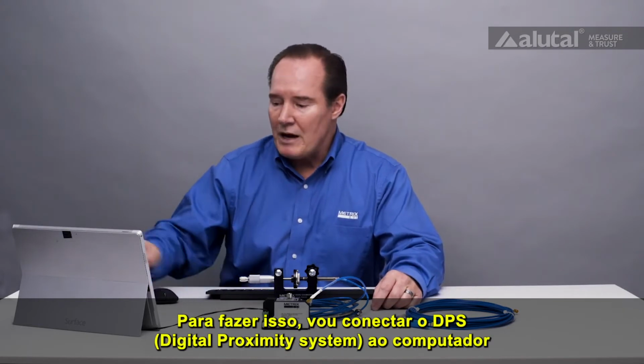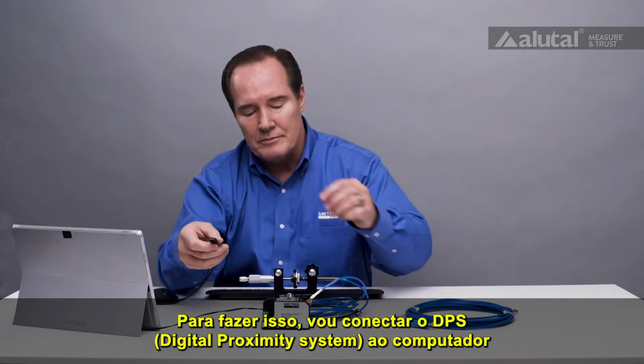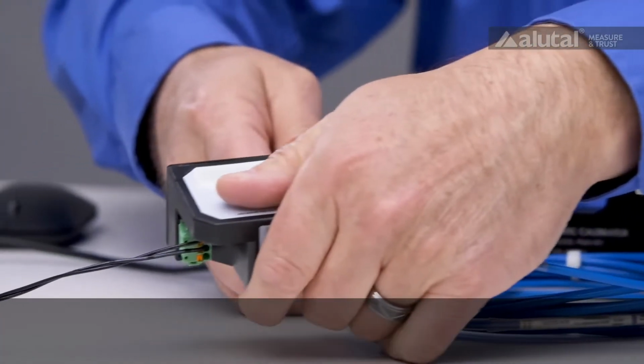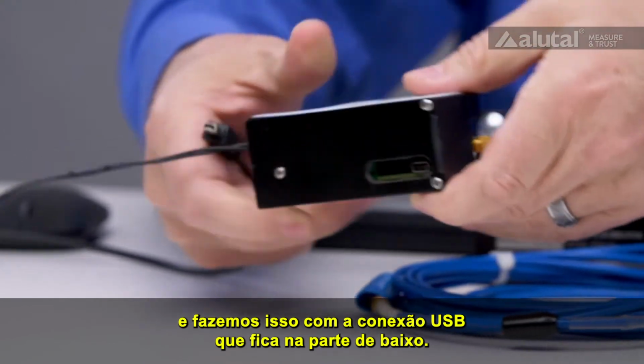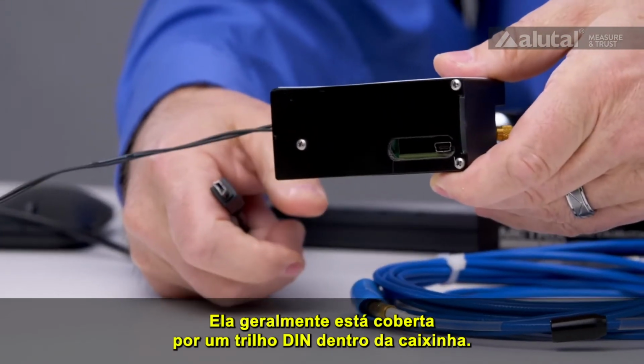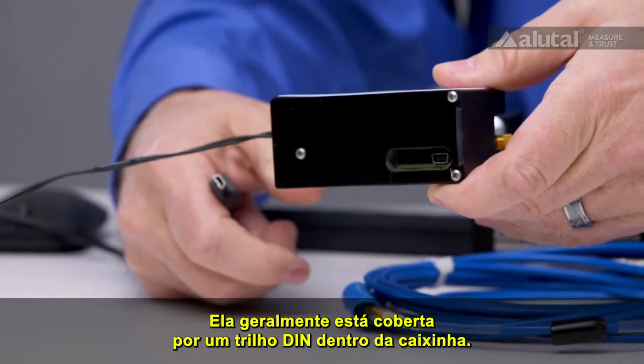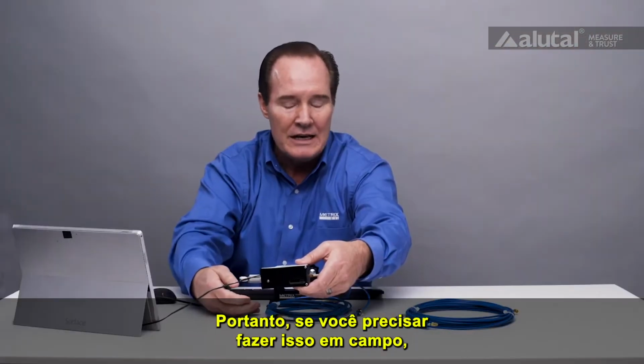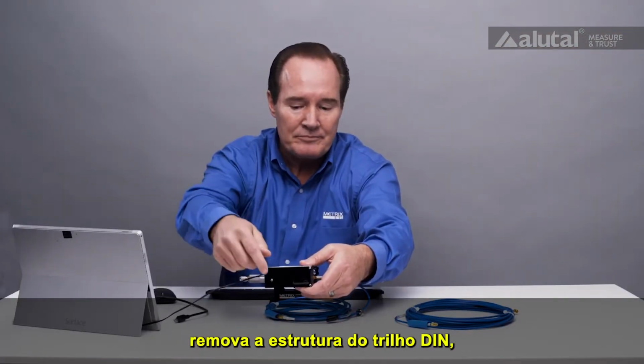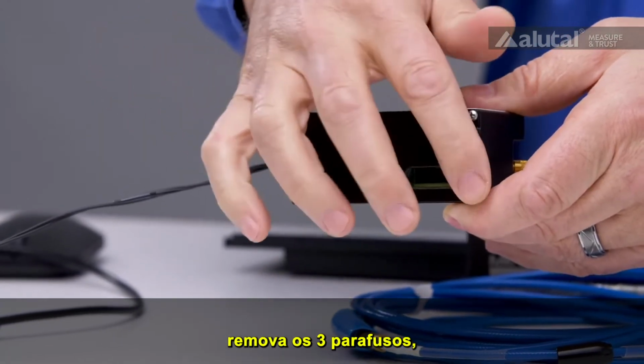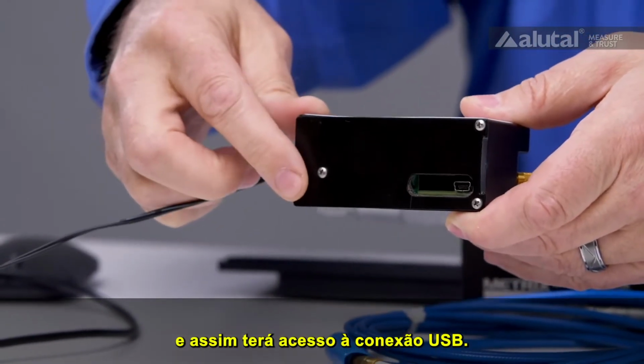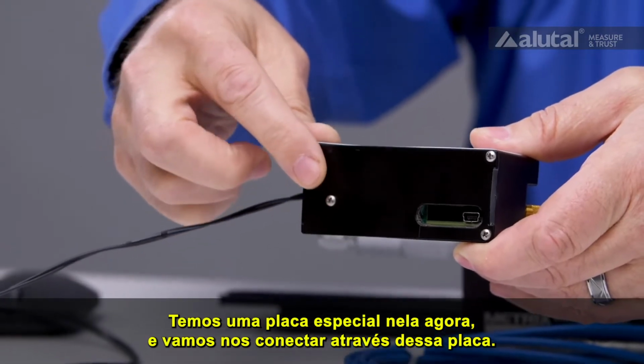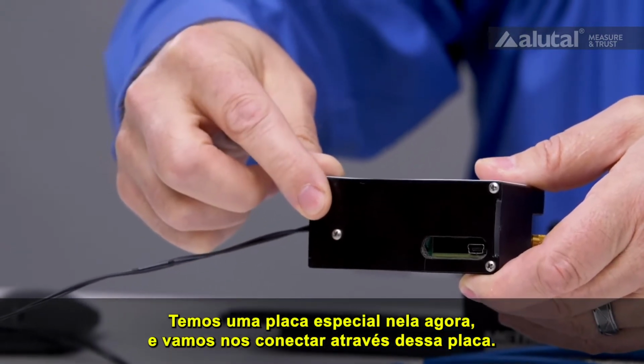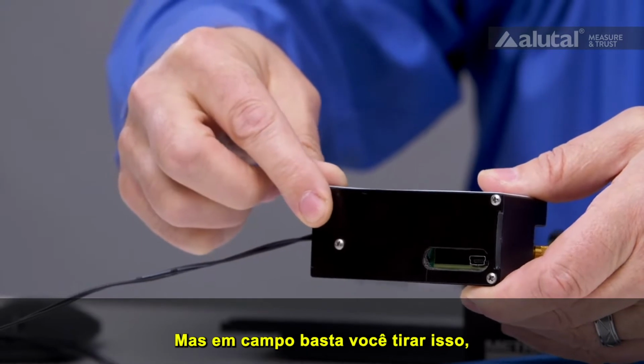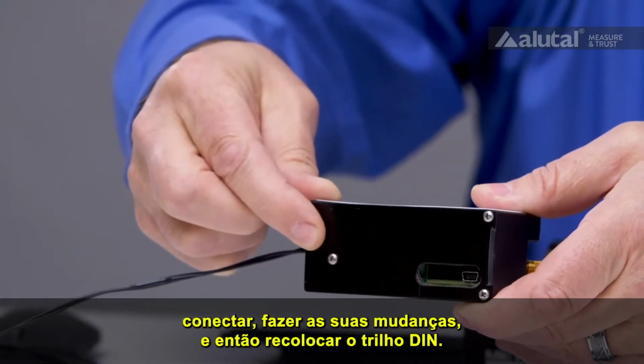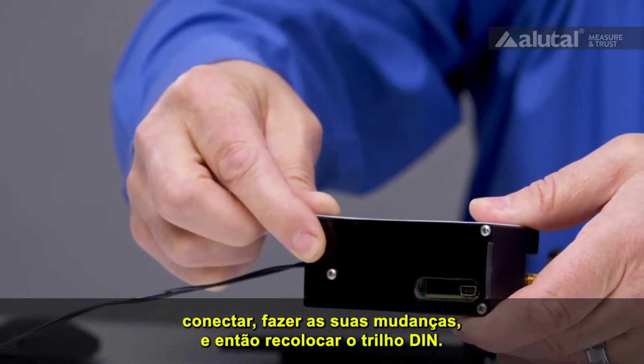So to do that, I'm going to go ahead and connect the DPS system to the computer, and you do that with the USB connection that's on the bottom. Now this is usually covered by a DIN rail mounting inside your cabinet. So if you need to do this in the field, you remove that DIN rail mounting, you remove the 3 screws that we have, and then you can get access to that USB connection. So we have a special plate on it right now, and we're going to connect through that plate. But in the field, you just take this off, you connect, you make your changes, and then you put the DIN rail mechanism back on.